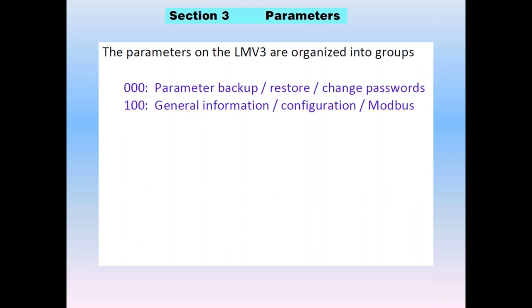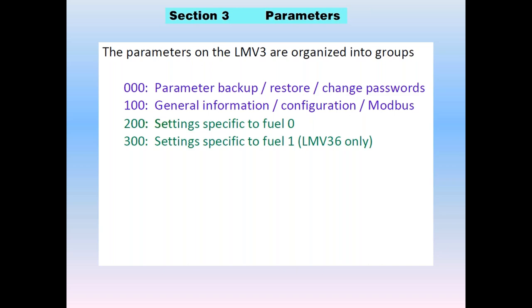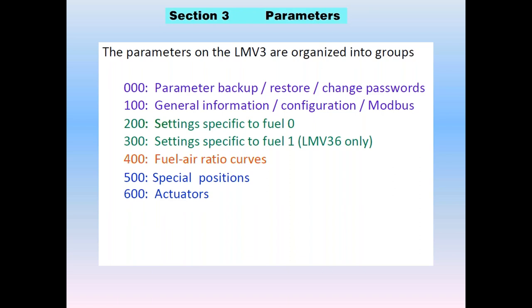The parameters are further organized into groups. The 0s and 100s cover backup, restore, Modbus, general information, and serial numbers. The 200s and 300s are setups specific to fuels — the 200s are fuel zero (gas or oil), and the 300s are for fuel one, used on the LMV36 dual fuel. Parameter 400 has one parameter: your fuel-air ratio curve. The 500s and 600s are dedicated to actuators, special positions, direction of rotation, and ramp times. 700 is strictly fault history — 21 faults. And 900 is operational data like flame strength and load controller. Breaking it into groups categorizes the parameters so you can navigate more easily.